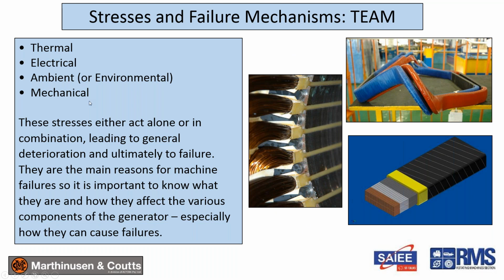It's also mechanical issues. And so I spoke here on the left about your main stresses in an electrical machine: thermal, electrical, ambient, and mechanical. And the stress that I'm going to concentrate on is actually thermomechanical. It's the mechanical stresses that occur due to differential expansion and contraction in a stator, due to the different heating of the copper versus the core.